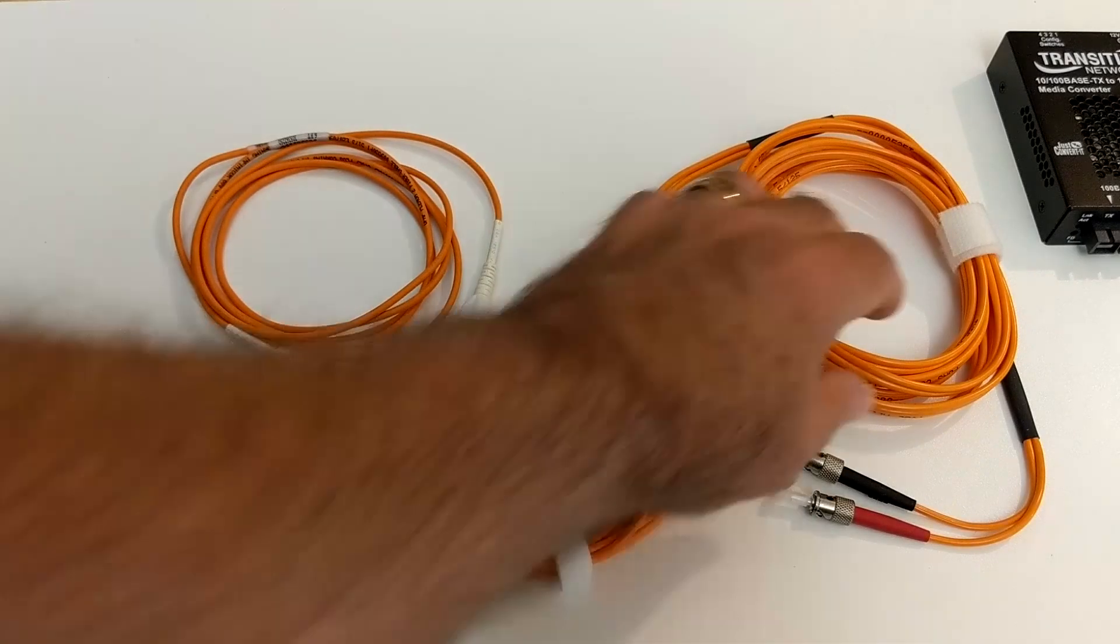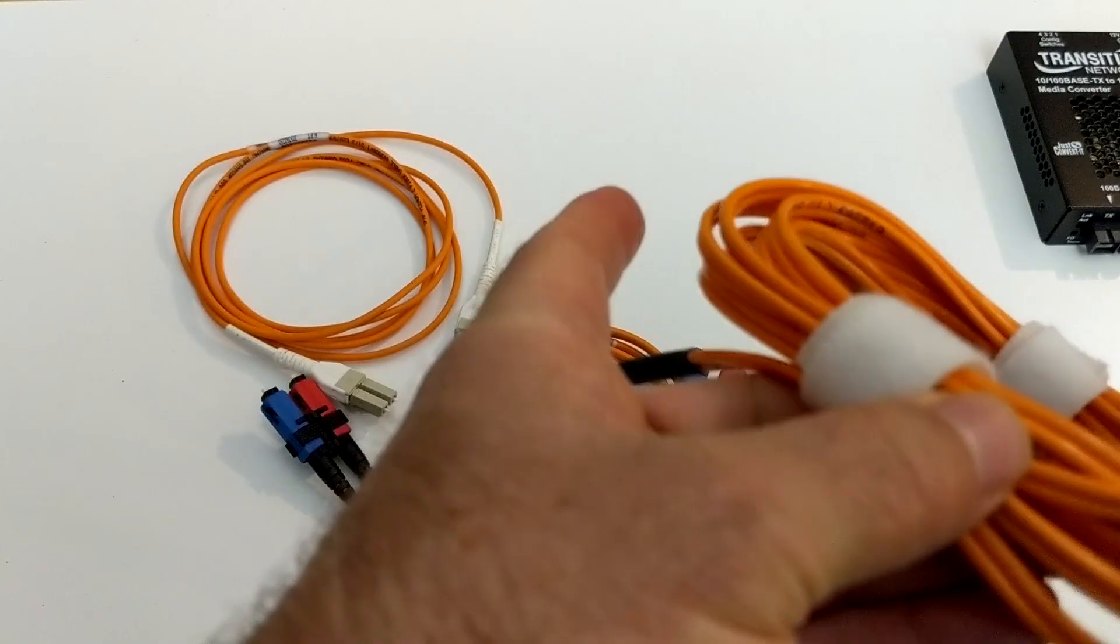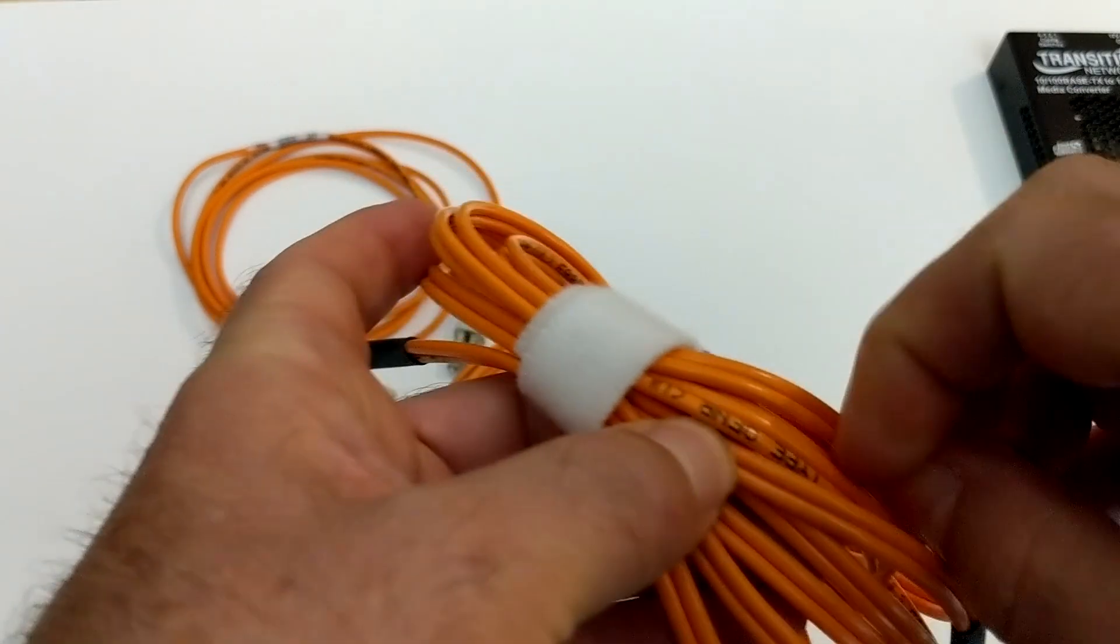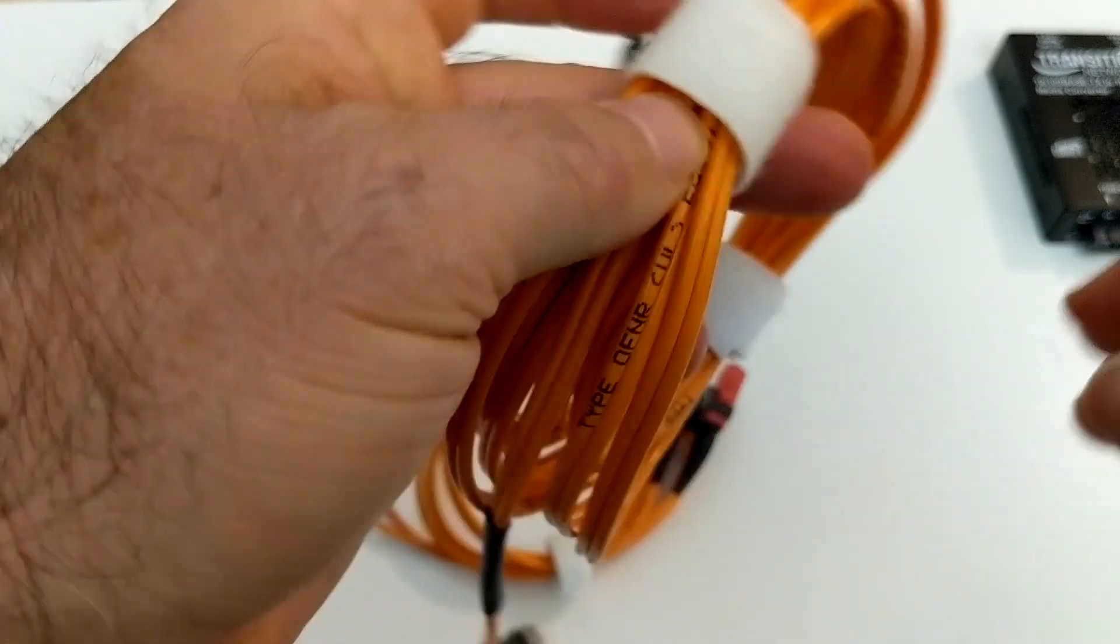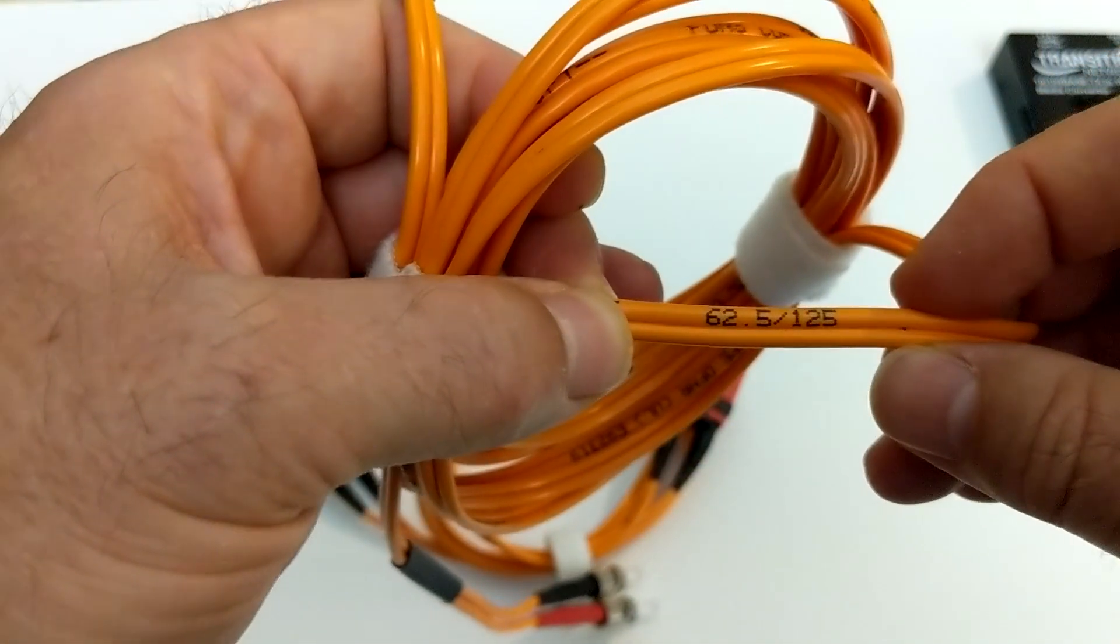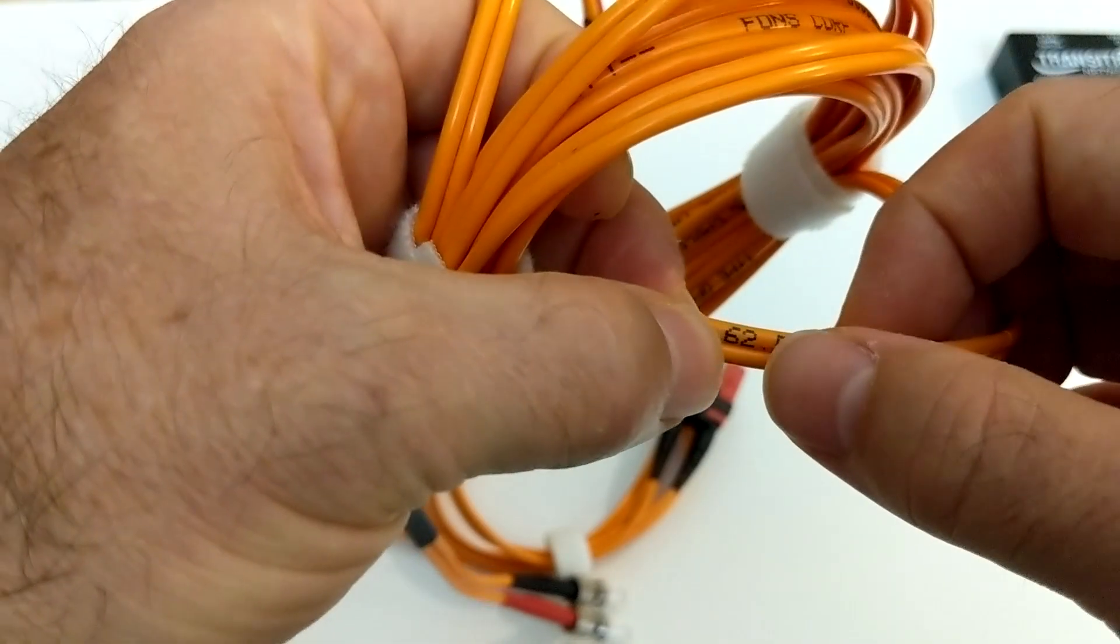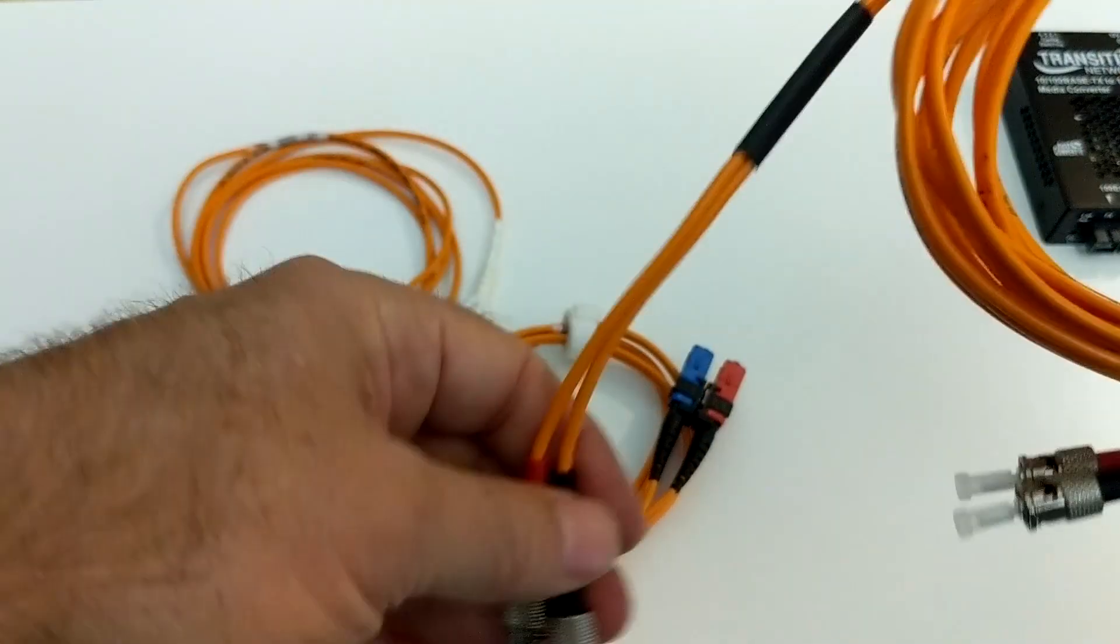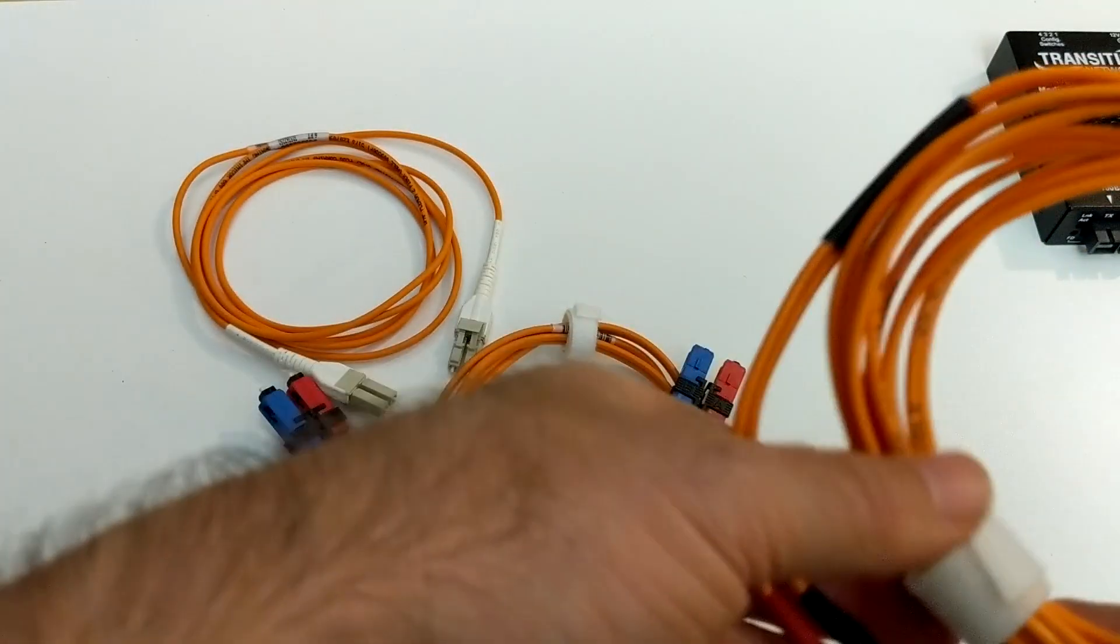And the way you can tell the difference is that oftentimes the cables won't have it written on them. But what you can do, and I know it's kind of small on the camera, so I'm not going to try to show you on the camera, but if you look closely, somewhere on the writing on the cable, it will have what's known as a micron size. And I don't know if you can see that, but right there it's saying 62.5 and 125. So the 62.5 is the inner diameter in microns of the fiber optic conduit inside. It's teeny. All right?